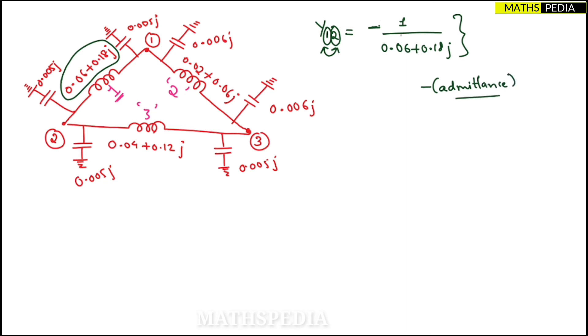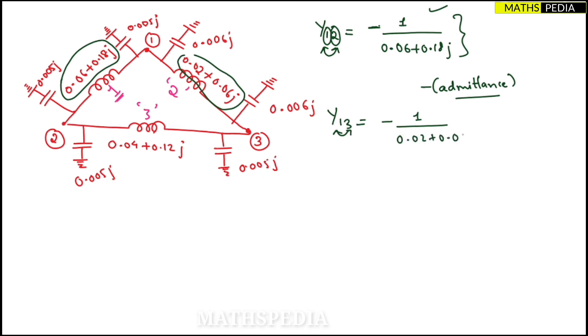So Y12 = −1/(0.06 + j0.18). Do not add half-line charging for non-diagonal or off-diagonal elements. The rule is simply: minus of the admittance, or equivalently minus one divided by the impedance between those two nodes.